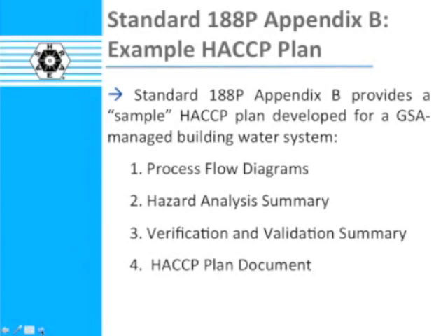And then those of us who are more analytical in orientation say, if we know that numbers in CFU per liter are not defensible analytically, that is to say, if you take a liter of cooling water and filter it, the recovery of Legionella from that filtered sample is so unpredictable. Sometimes recovery is much greater than 100%. Other times it's 20%. It's not a quantitative analytical filtration, especially for complex water matrices like cooling water. But even in clean water, like from hospitals, filtering large volumes of water is not quantitative. Therefore, those who are more pure science types will say that generating data that we know is not analytically defensible is not to be recommended.